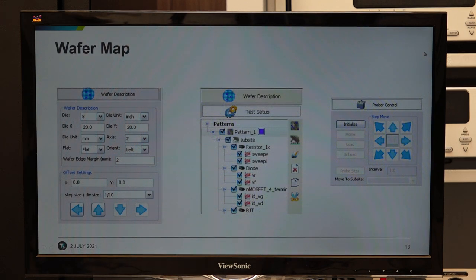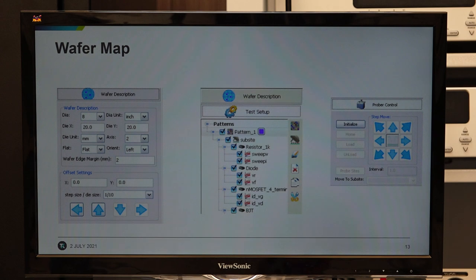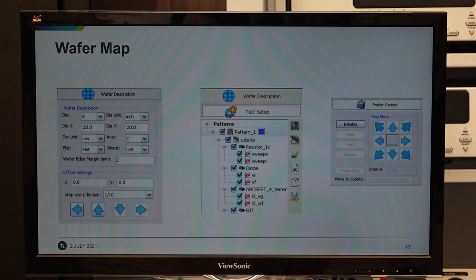The test setup has a top-down tree structure where you define wafer level, then choose subsite level, then device level, and then test levels can be programmed and walked through in sequence mode. For each device level and test, libraries with built-in test routines are available — the user only needs to change the conditions for the test. Prober control settings allow the prober to move left to right, front to back, or automatically load wafers from cassette to stage.